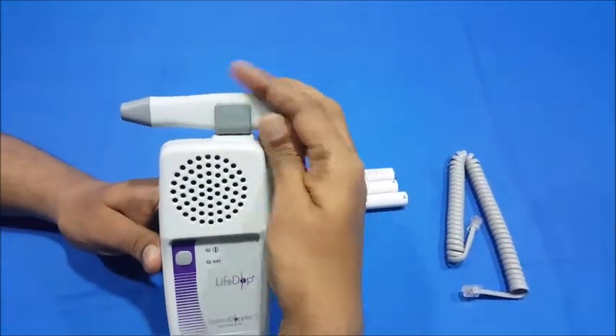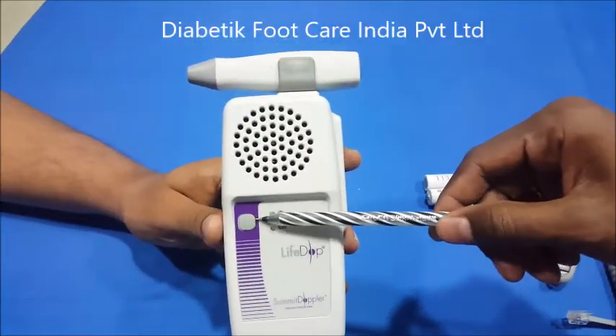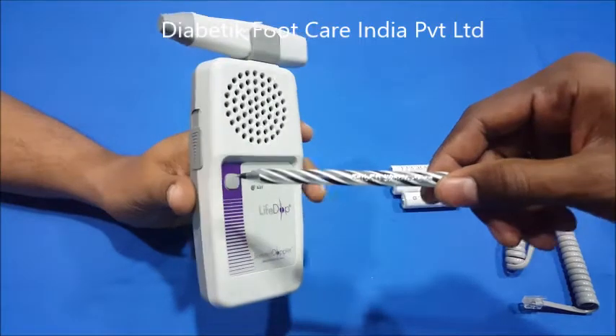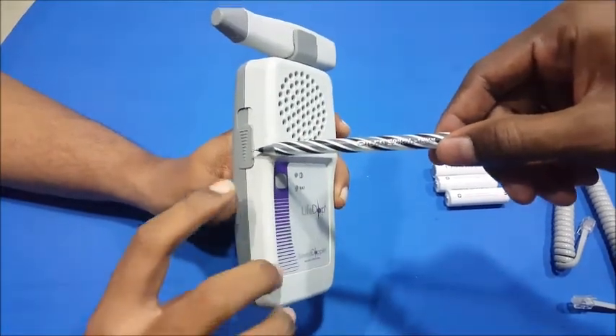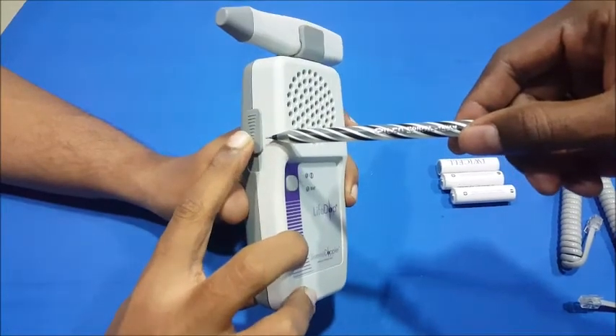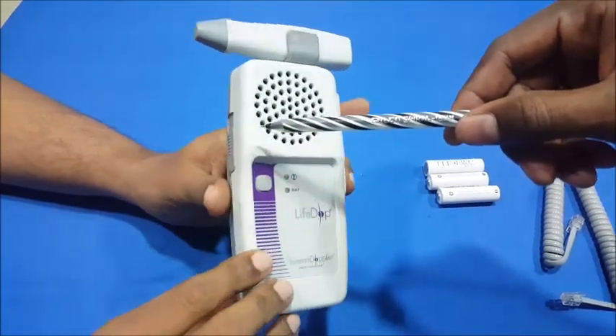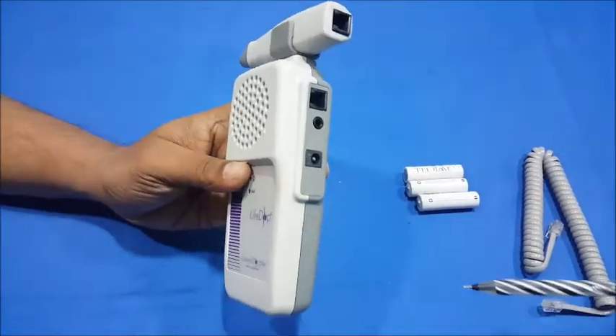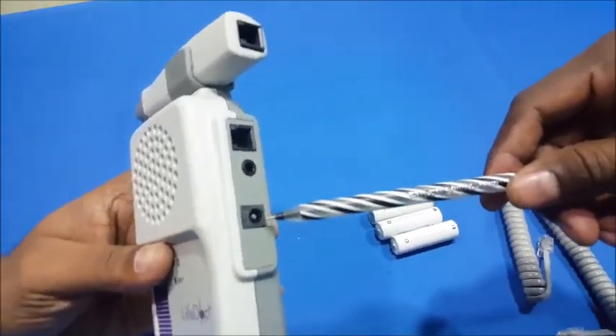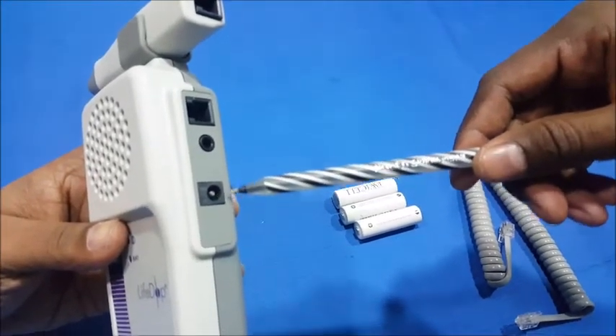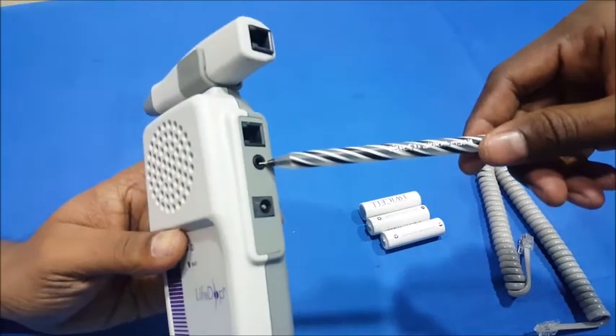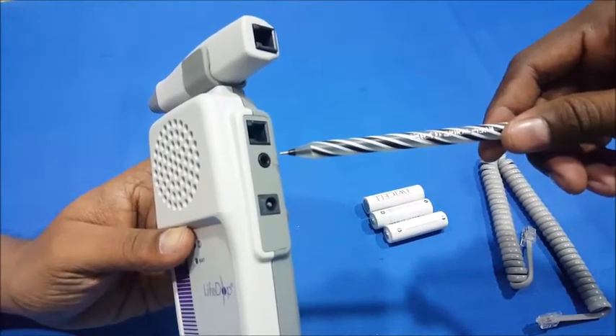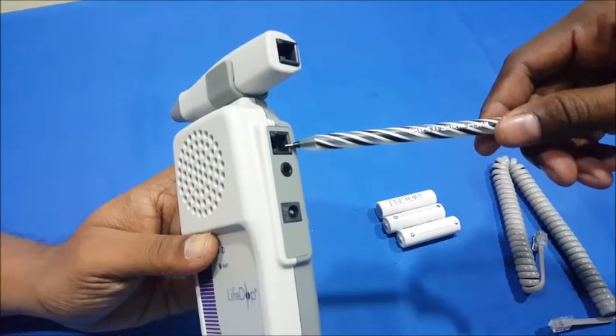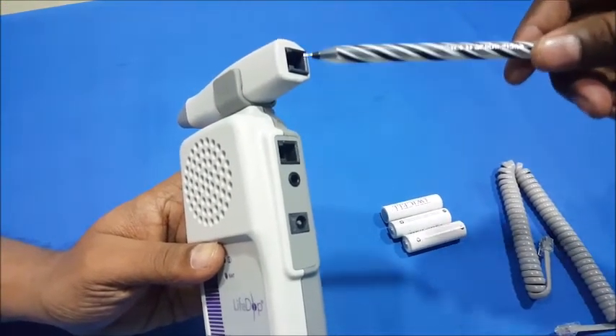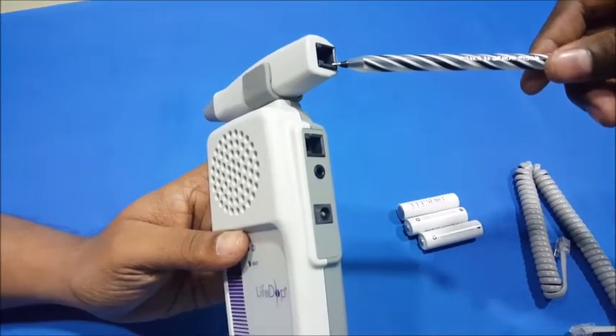Now we are seeing the main unit, and on top of that is the 8 MHz Doppler ultrasound probe. Now see the on-off switch. To switch on the machine, just press it once. On the left side you will see a slide switch, which is the volume control: push it up to increase, push it down to decrease the sound. On the right side you have 3 controls. That is the charger point; you can connect the external charger for charging the battery. The next is the headphone point; you can connect the headphone if you want to hear the sound privately. And this is the connector for connecting the probe cable. You have to connect one end to this and then the other end to the probe.